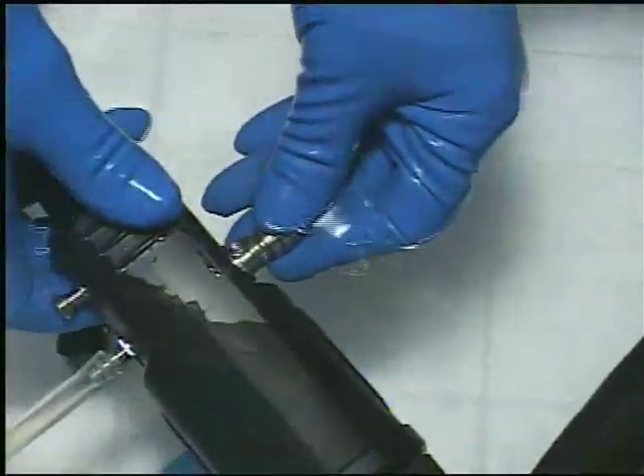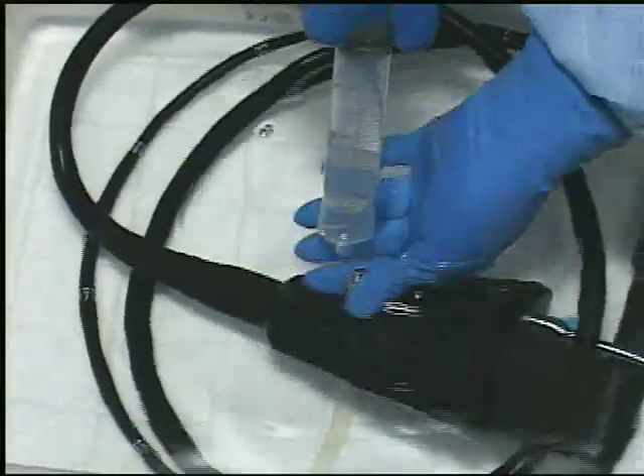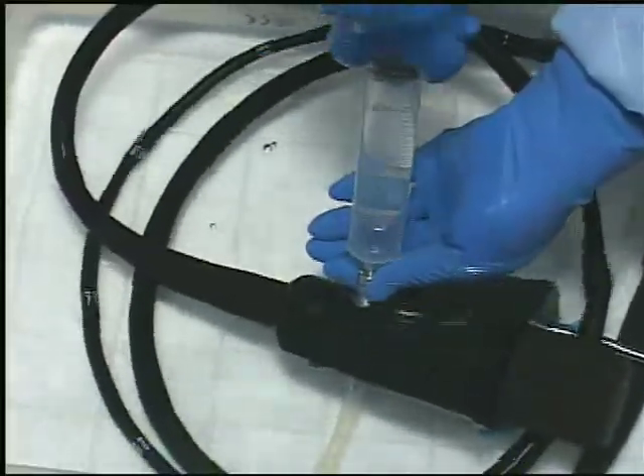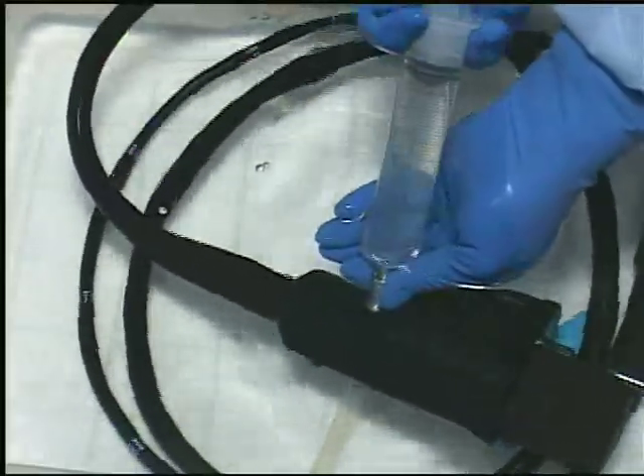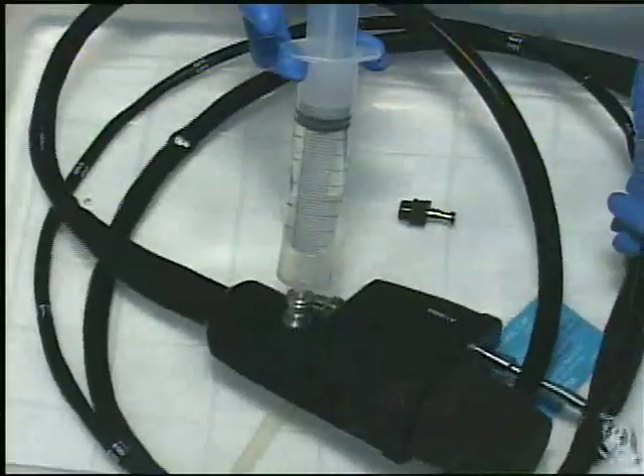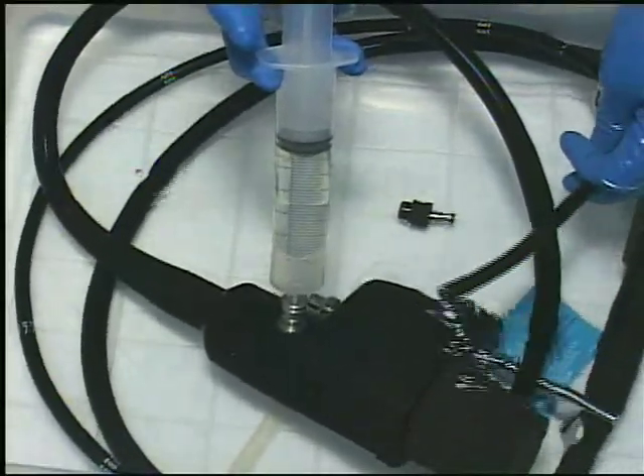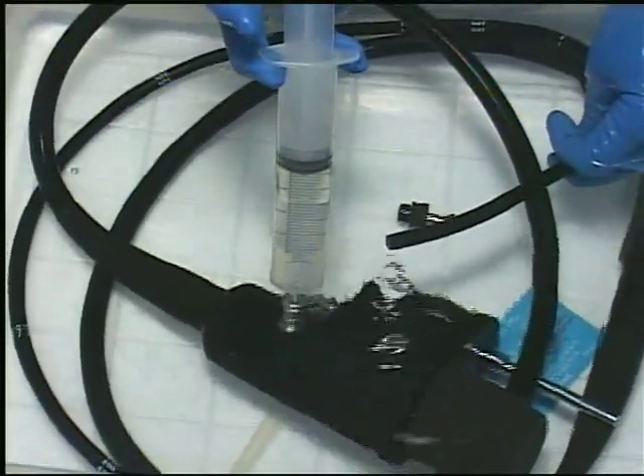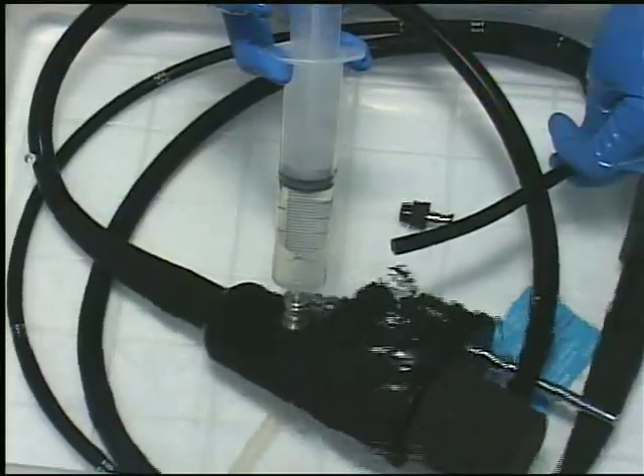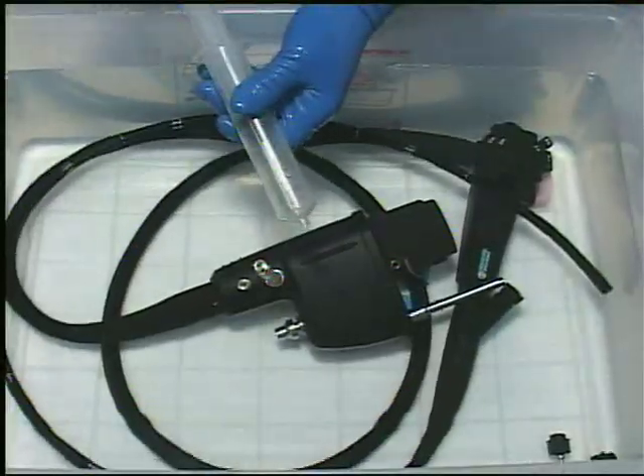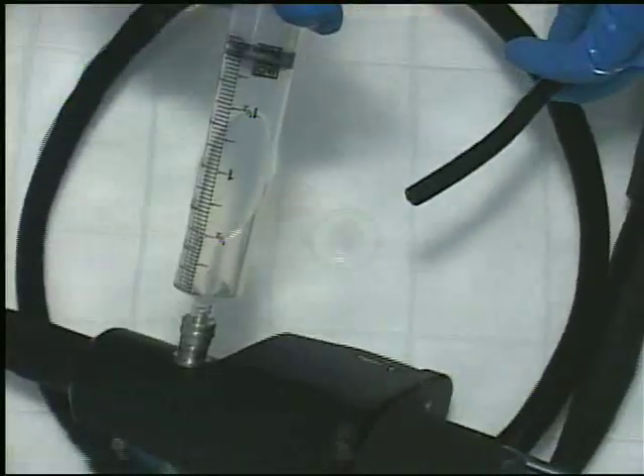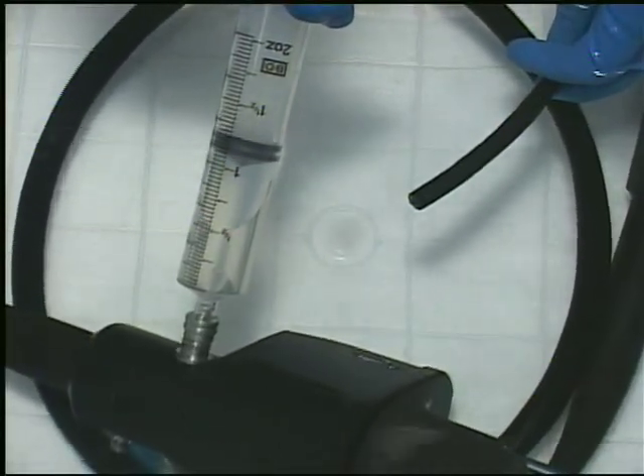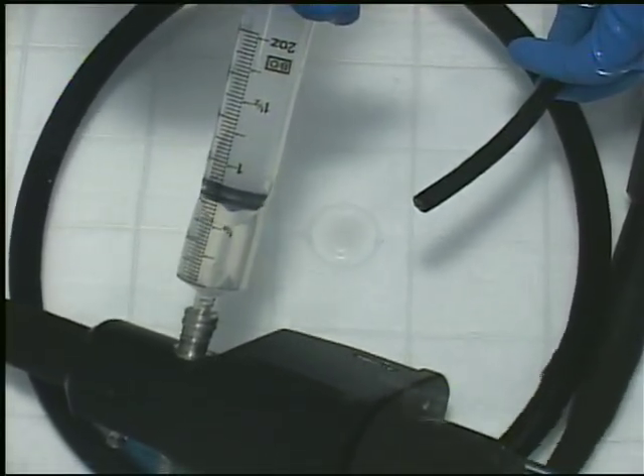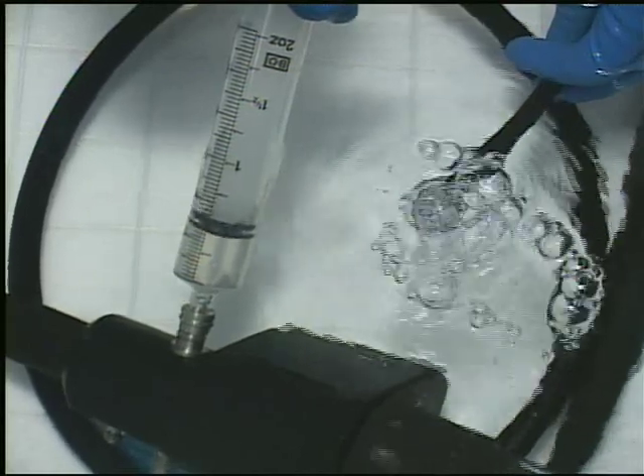Reattach the air-water cleaning adapter OFG17. A syringe filled with sterile water should be attached to adapter OFG17 to flush disinfecting solution from the air and water channels of the scope. Most high-level disinfectants require triple water rinses. Fill a syringe with air and flush through the air and water channels several times to force any residual water out of the tubing and nozzles.